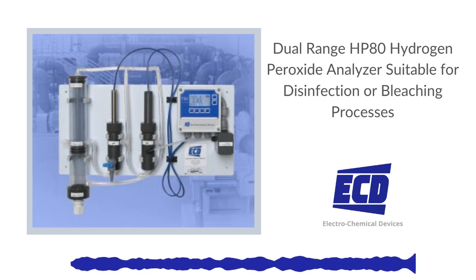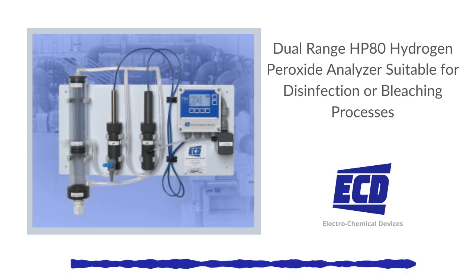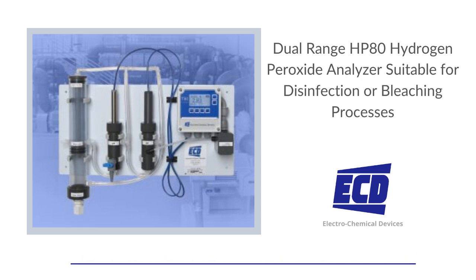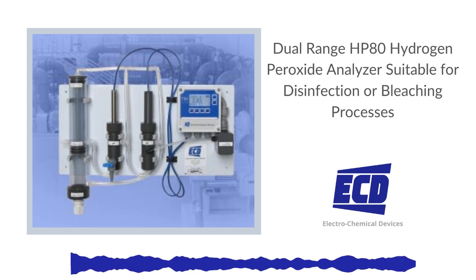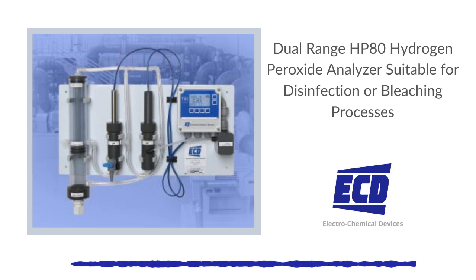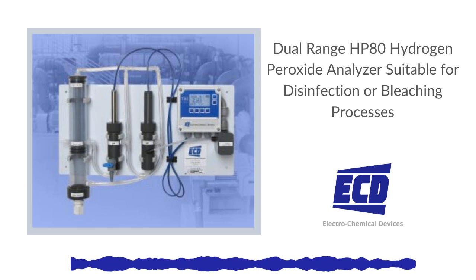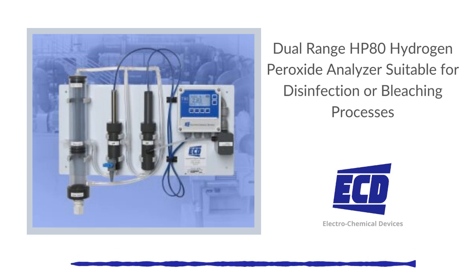A constant head flow control device, CFD, maintains the optimum flow rate moving past the sensor for sampling purposes. The CFD's automatic flow control capability eliminates the need for pressure regulators and rotameters, which are required by many other H2O2 analyzers, to reduce system maintenance and lifecycle operating costs. The minimum flow rate required by the CFD is 10 gallons per hour, and the maximum flow rate is 80 gallons per hour with the sample draining at atmospheric pressure.